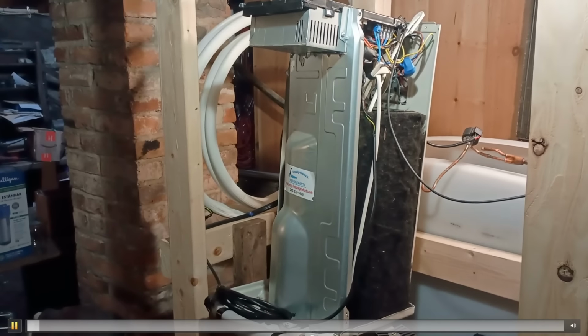Now we'll look at inside the tank. So looking down in here, we can see the evaporator. We can see two temperature probes. One is coming off from the mini split. The other one is controlling that circulating pump, so below a certain temperature, it'll kick on. On the left, there is a return line. That's a circulating return. On the right, that's the circulating return from the ground loops.